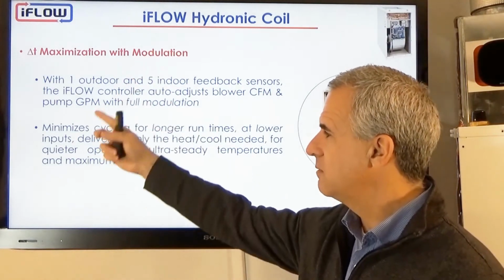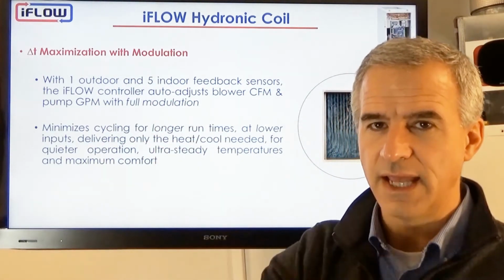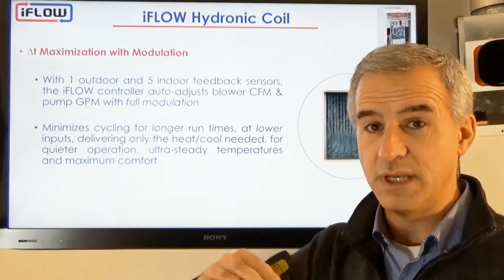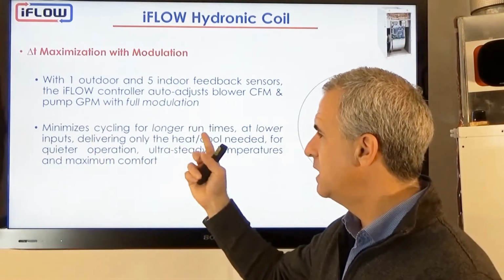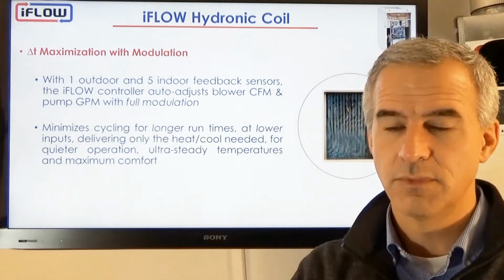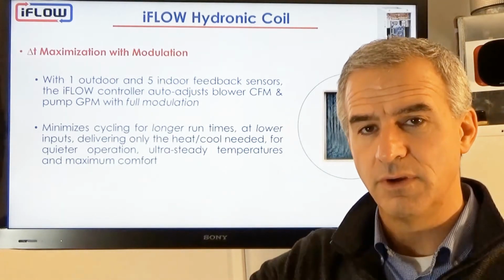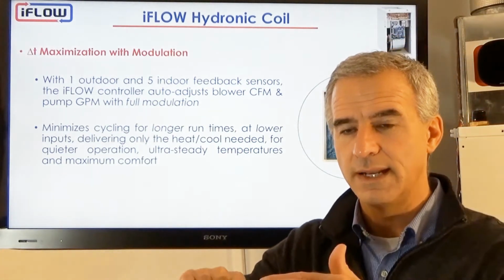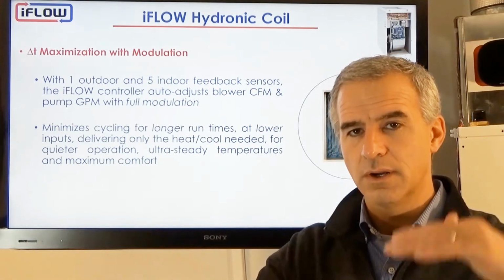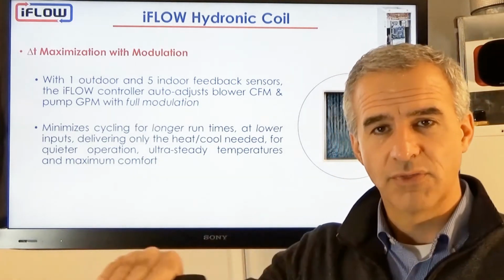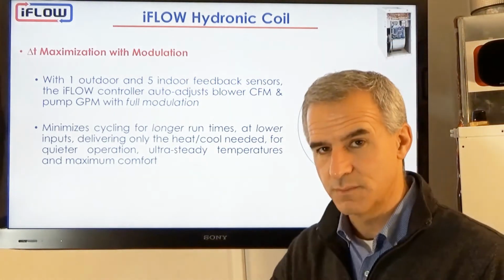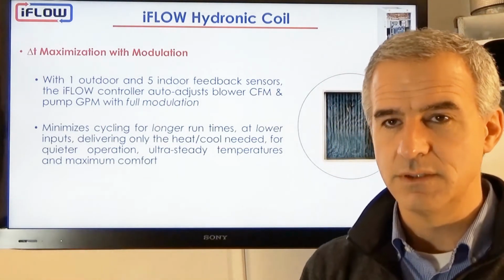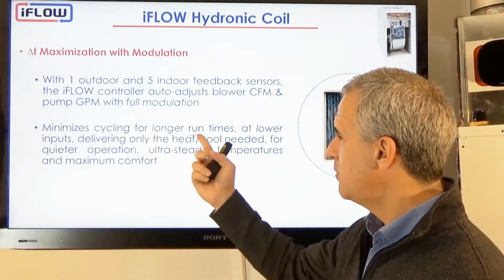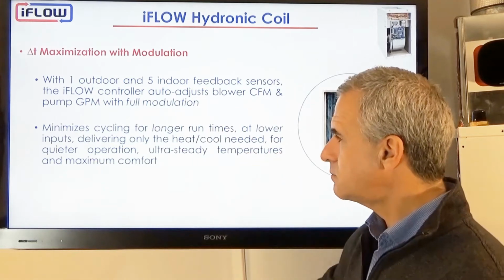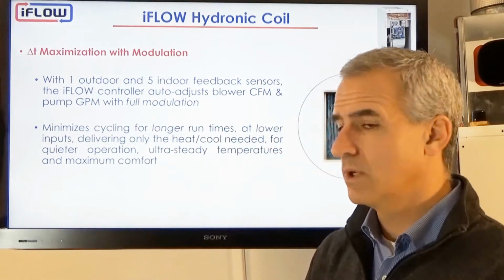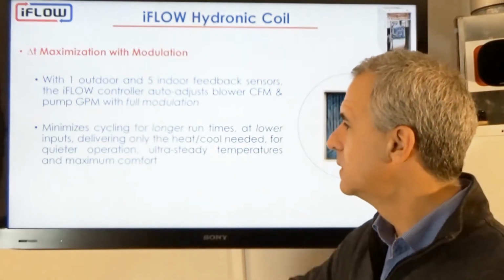With the modulation, because we can modulate down to any speed, if you will, this minimizes cycling. So if we need 35,000 BTUs, we can run at 35,000 BTUs. We don't need to run at 60,000 and go on and off and on and off. We can run at 35,000 BTUs or 30,000 BTUs or 42,000 BTUs, whatever the case may be. So that makes for longer run times at lower inputs, so we're not over delivering.